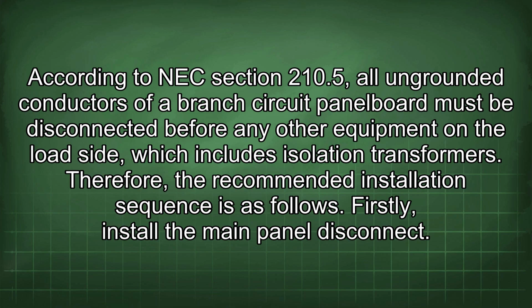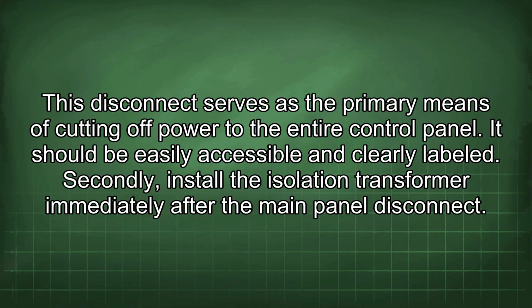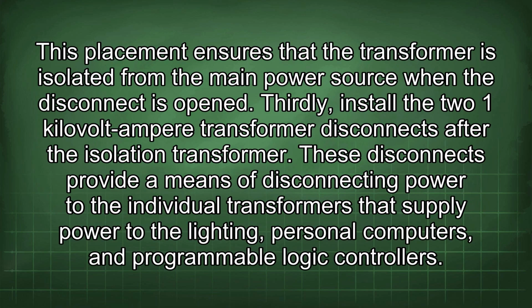Firstly, install the main panel disconnect. This disconnect serves as the primary means of cutting off power to the entire control panel. It should be easily accessible and clearly labeled. Secondly, install the isolation transformer immediately after the main panel disconnect. This placement ensures that the transformer is isolated from the main power source when the disconnect is opened.